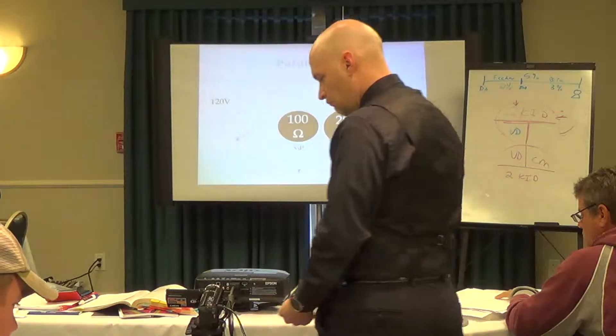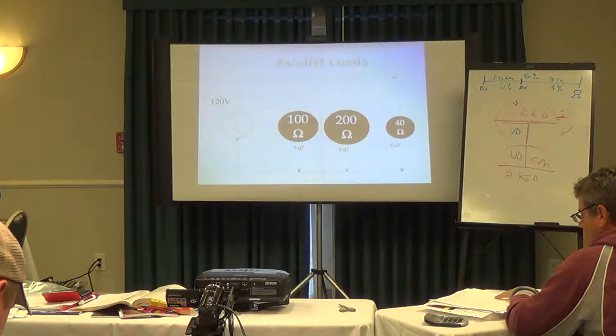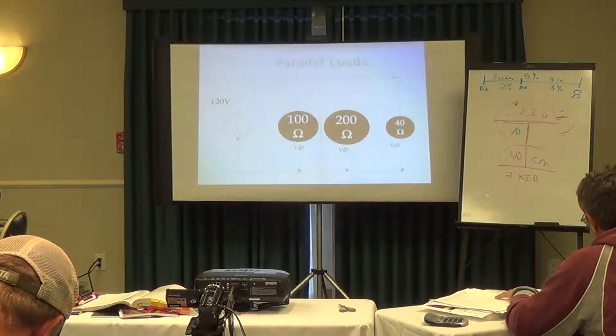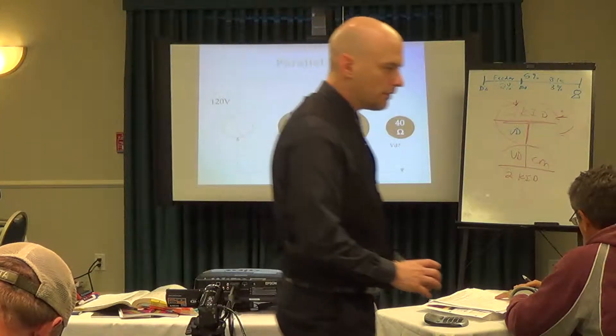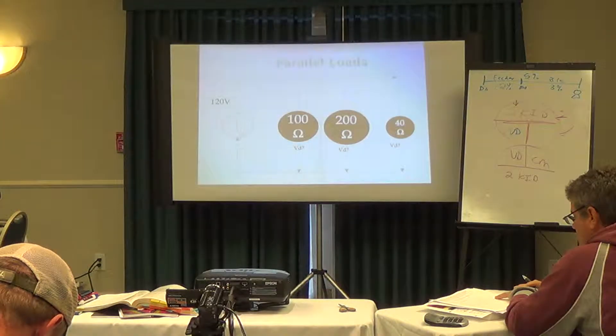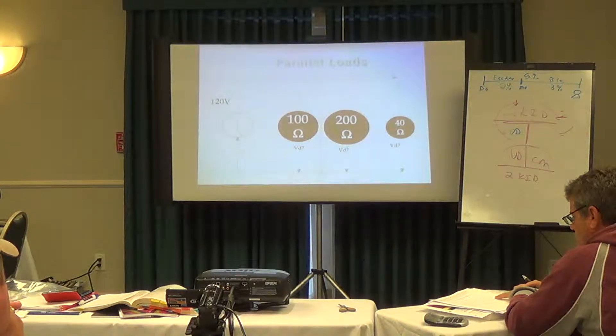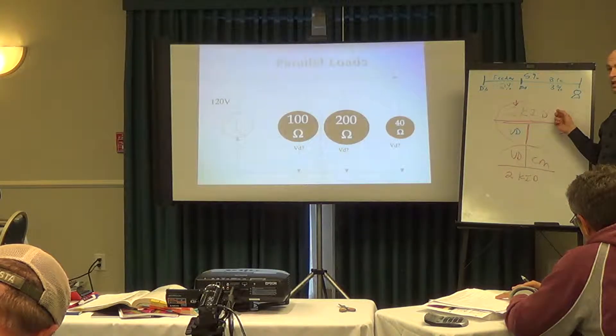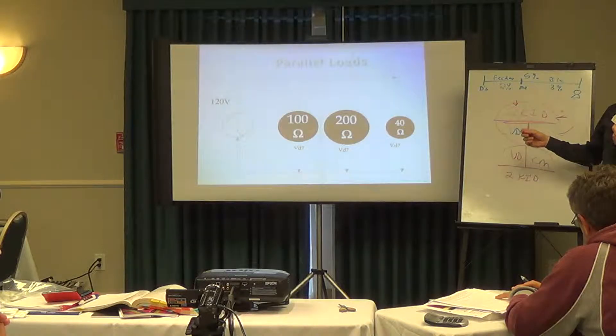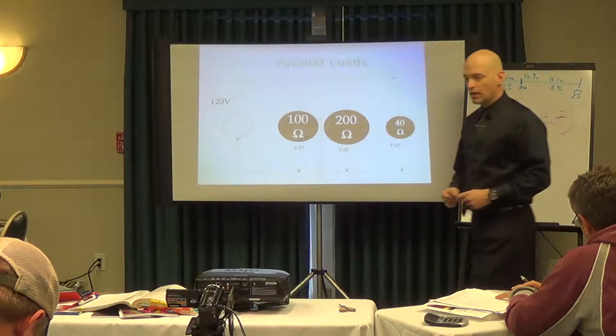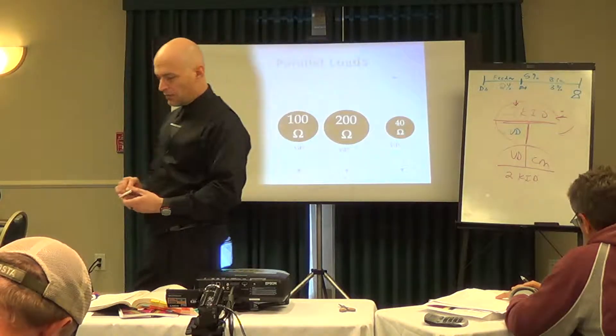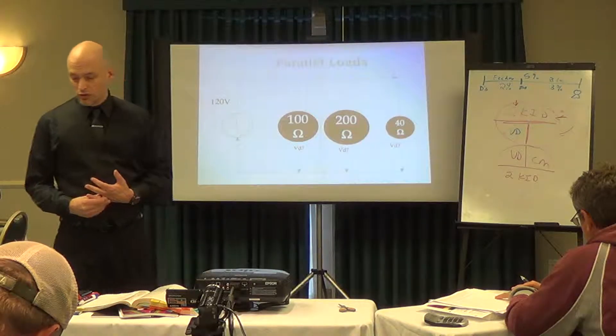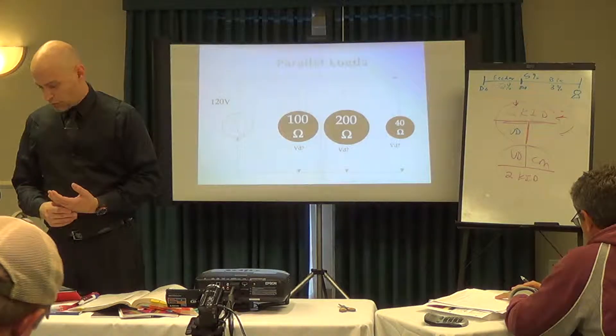If you look at the top there, I've got 3%, 2%, 5%, so I've got all three of your losses, and the system voltage is on the column there. In this case, we're looking at a 240 volt, 3%, 7.2 volts. Take the sting out of it. And that's what that sticker's for. You only use it for these types of formulas, and so if you see a VD anywhere other than that original example. So that's the maximum amount you want to lose on any one of those system voltages, and in this case, at 240 volt, 3% branch circuit, you're looking at 7.2 volts.